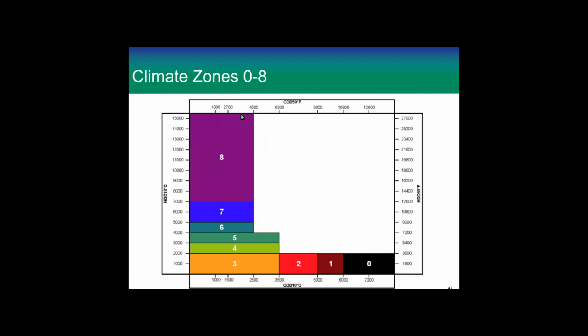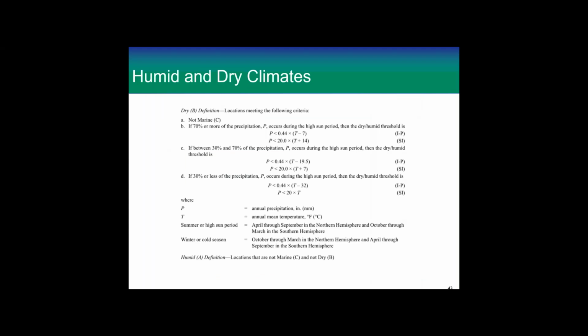So it's good to recognize it, because if you'll notice, it's all based on heating degree days, and humid and dry climates are also based on rainfall, precipitation. It doesn't ever mention humidity, which is very important to think about as a mechanical engineer. There's not anything in the standard when we talk about climate zones that talks about humidity. Now you may think, well, it rains a lot, so you've got a lot of humidity, but that's not necessarily true. Also, in places where it snows a lot, and they're considered to be moist or A environments, they sometimes complain that it's not the same as being in a hot, humid spot, even though they get a lot of snow.